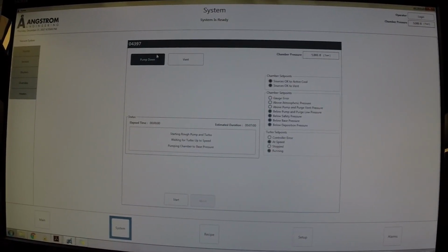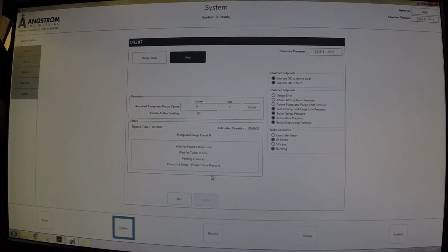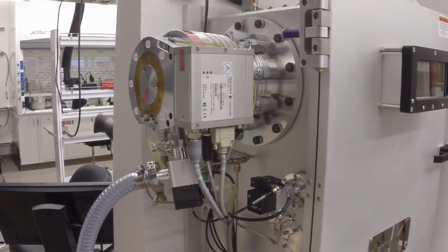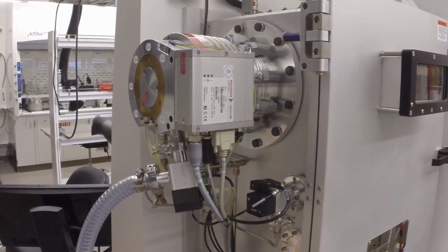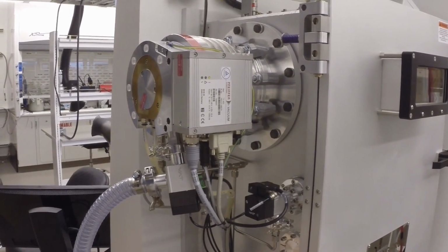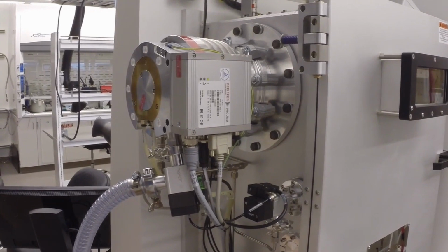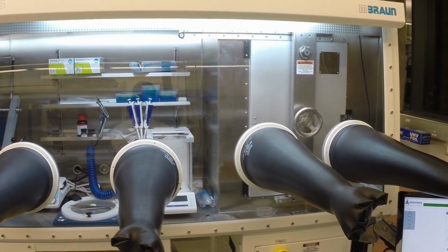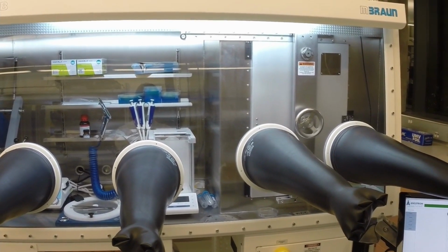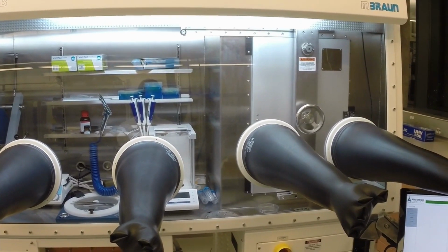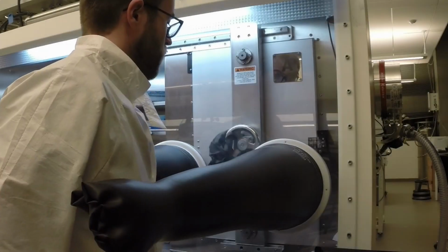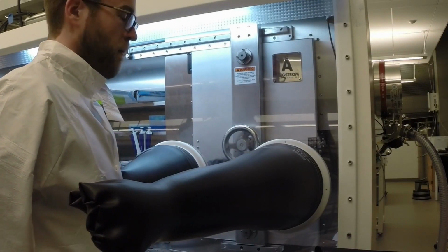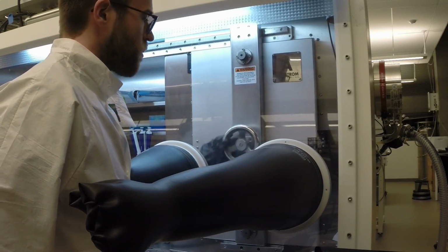Currently, the chamber is under vacuum and must be vented using the software to open the door. Small volumes of nitrogen are introduced to the turbo pump to slow it down in a controlled manner. This decreases the vacuum the pump is pulling out of the chamber. After a couple minutes, the evaporator begins filling with pulses of nitrogen from the box until atmospheric pressure is achieved. Upon reaching ambient pressure, we can open the door and begin loading sources and substrates into the chamber.